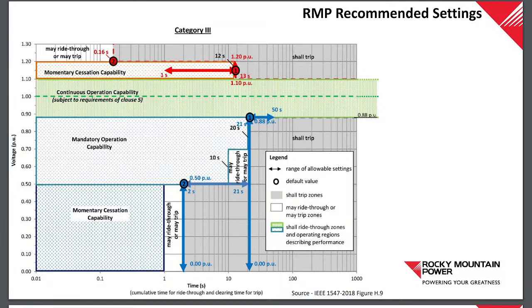But once you start looking at this graph for a few months and think about it in the middle of the night, it makes sense to you. So the shall trip, anything longer than 20 seconds, if we're looking at that one dot, 21 seconds at 88%, it's going to trip. But it won't trip for 20 seconds. So it's going to wait to see if that disturbance is going to fix itself, right? If we have a fault, or a frequency or voltage fluctuation that is temporary in nature, we're just giving it time to get back into that green range, and then everything's good. So we love this idea. We don't like the existing generators, the inverters, just tripping offline.